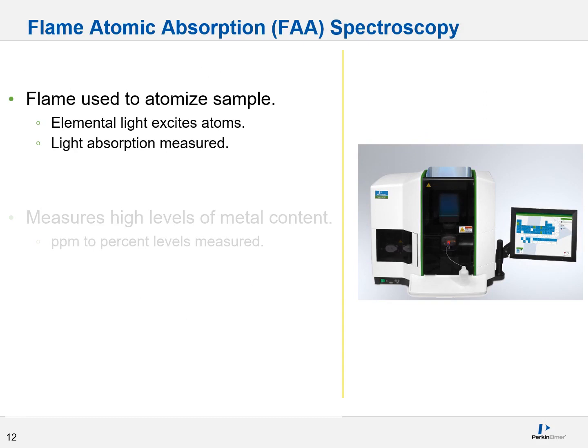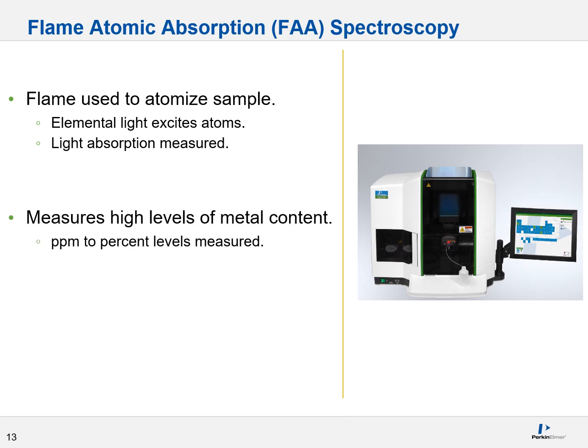In flame atomic absorption spectroscopy, or FAA, a flame at about 2,500 degrees Celsius is used to atomize your sample. The atomized samples are irradiated with element-specific light, and the amount of light absorbed is used to back-calculate what and how much of your particular metal you have. This technique is used to measure high levels of metal content, usually from the ppm to percent levels.